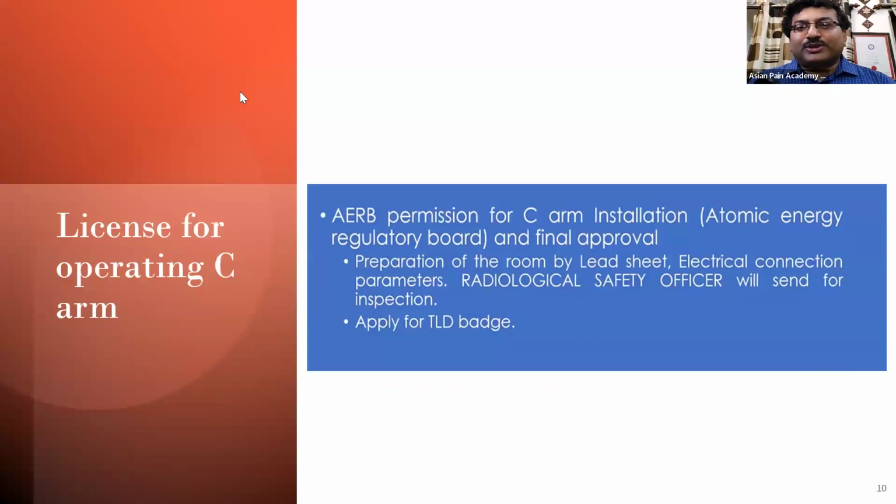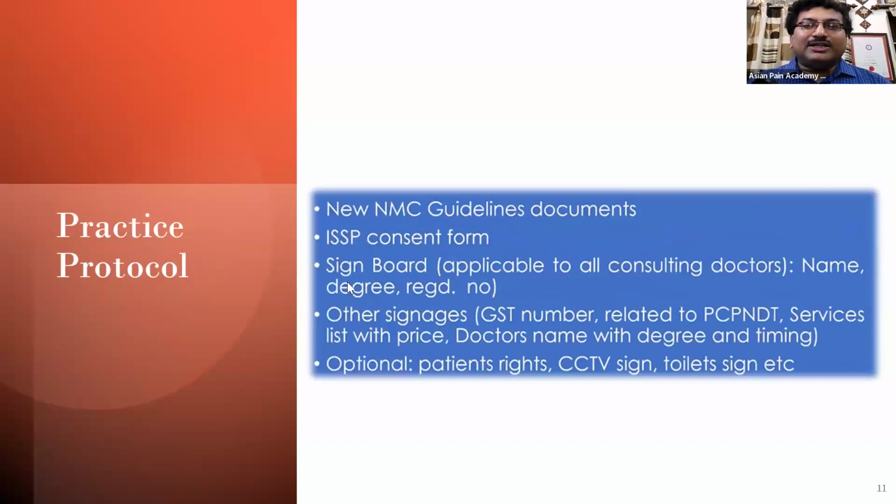Now, for the fluoroscopy, we will require an AERB permission for the C-arm installation, and you have to apply for the TLD badges. So these are all ideal things, but a lot of deviation occurs all over India. Ultimately, you have to maintain whatever is running in your state. Now coming to the practice protocol. First of all, you have to follow all the NMC guidelines.